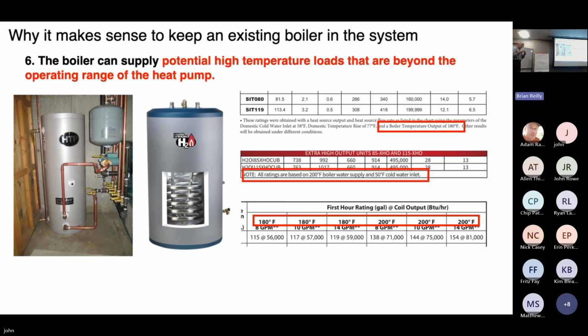So there may be logic in saying, I don't want to tear out this and put another $2,000 into the system to get a better tank. I could set up a system where the boiler heats the tank and the heat pump does everything else. Or, and I'll get to this, I could set up a system where the heat pump with a separate tank does preheat to maybe 110, 120 degrees, and then send the preheated water into the existing tank and let the boiler top it off. That's another possibility. But there are times when heat pumps just simply can't make the temperature that's necessary for the load.